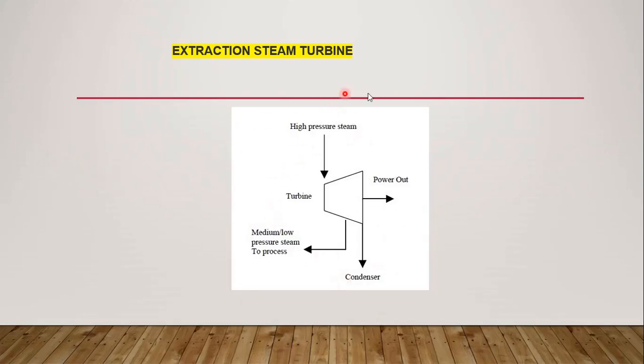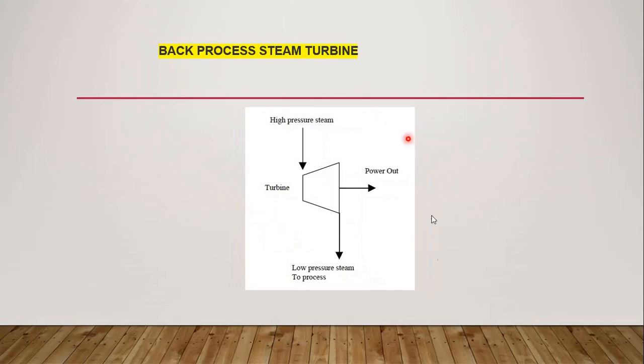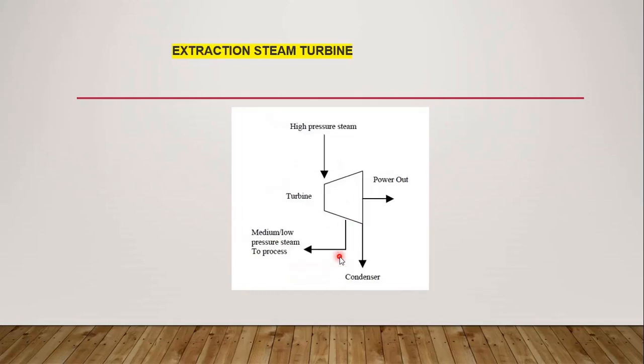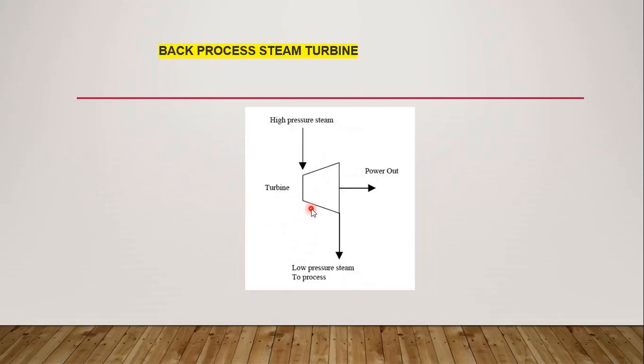These are somewhat critical turbines and the control logic is also a bit more complicated compared to the non-extraction turbine. The other category is the back pressure steam turbine. The major difference is that high pressure steam is coming in and you have only one outlet. In the extraction steam turbine, steam comes in with one outlet going to the condenser and another going to the process, but in the back pressure steam turbine you can see only low pressure steam going to the process.